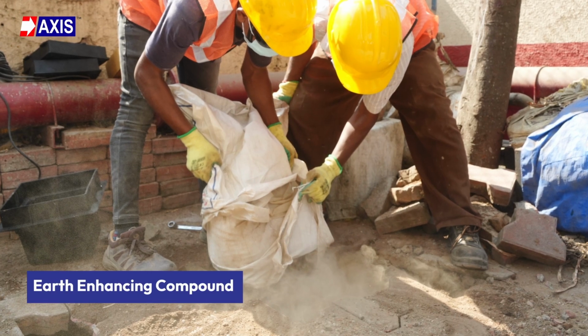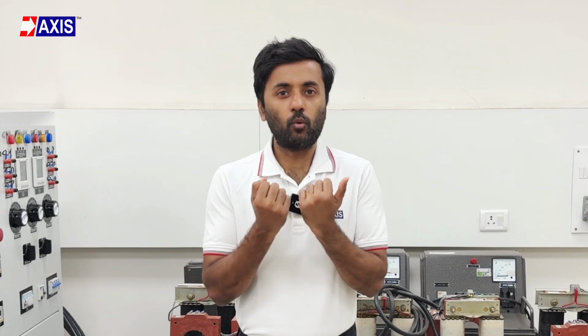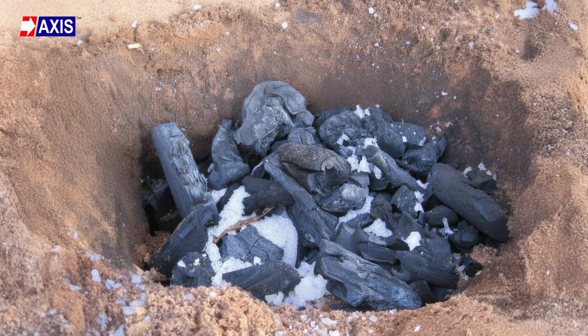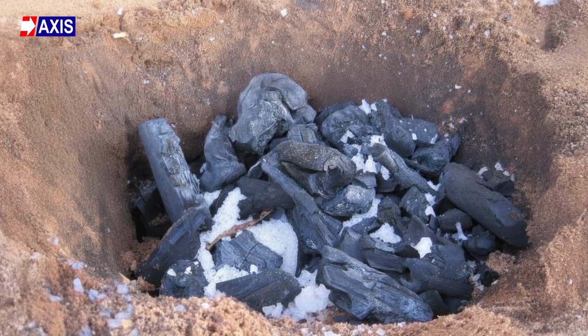Firstly, starting with earth enhancing compounds. This compound is made from a mix of minerals that has lower soil resistivity. Its main feature is the ability to absorb and hold moisture, which helps your earthing system maintain a consistent electrical resistance over time. However, to save cost, some people use salt and charcoal instead of earth-enhancing compounds.